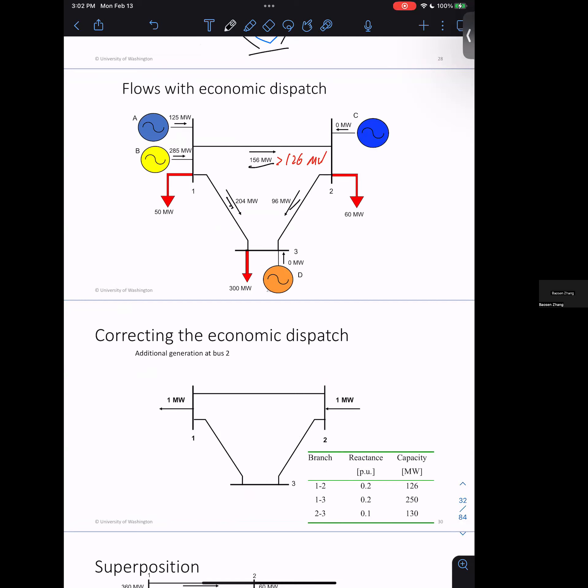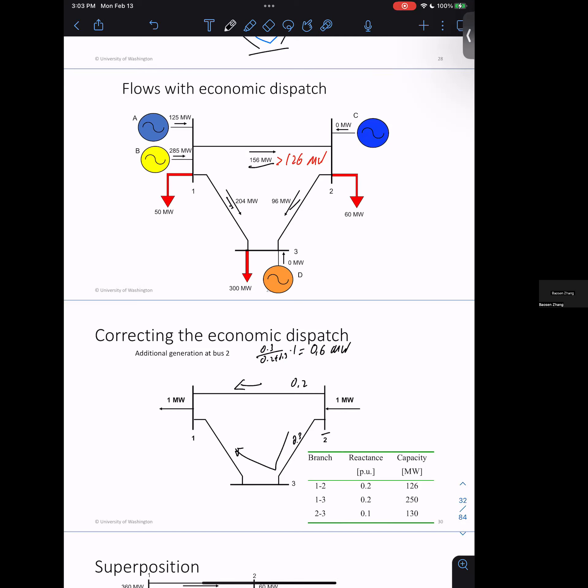Your goal is to check what happens if you start generating at bus two. Push one megawatt into bus two, and it breaks into two paths. Looking at the reactances: this line is 0.2, and the path from two to three and three to one has reactance 0.3. So one megawatt divides as follows: on this direct line you have 0.3/(0.2+0.3) = 0.6 MW, and on the other path 0.4 MW.